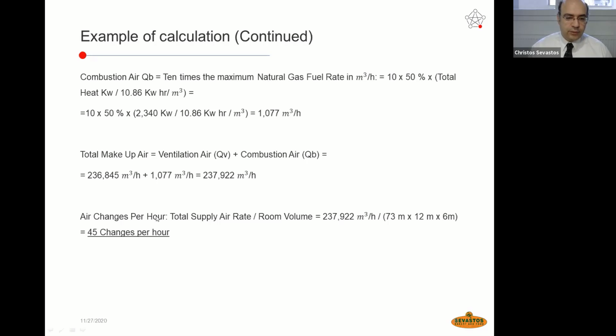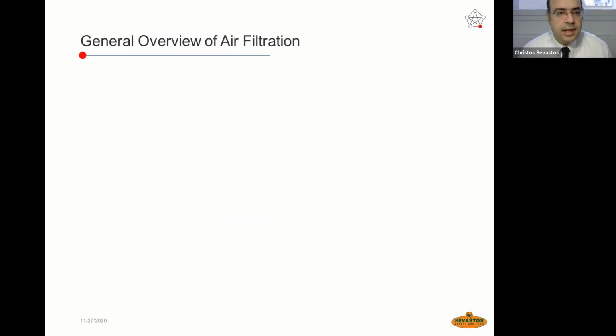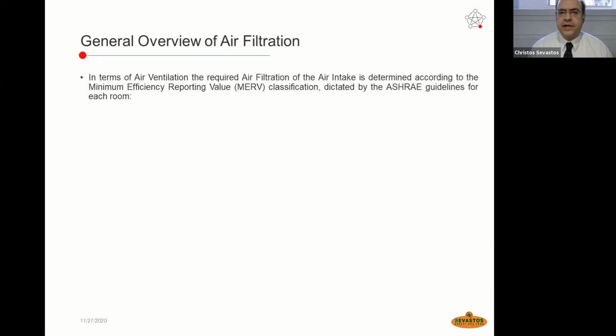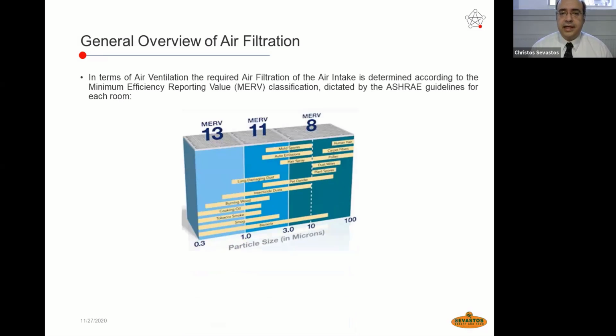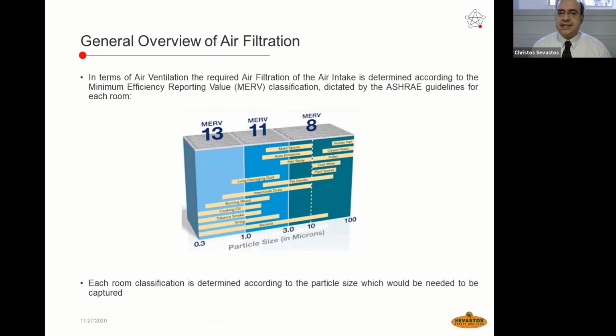So after all those calculations, we need to define this kind of air exchange rate, which is very important in order for us to be able to design, let's say, our oven room. Now, apart from air ventilation inside the room, if we would like to make an overview regarding the possibilities of air filtration, this is needed in cases where, apart from pure, non-filtrated air supply, we need to define air filtration in the air intake. Then we need to define the minimum efficiency reporting value. This is a classification of the minimum efficiency reporting value dictated by the ASHRAE guidelines.